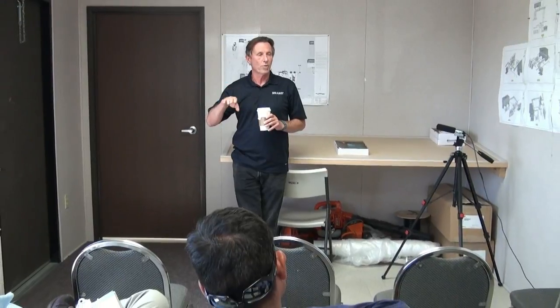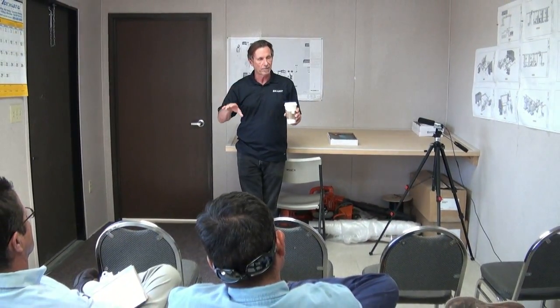That's a good question. As the compressor is spinning, there's a certain amount of kinetic energy in that shaft that's spinning. As soon as the compressor senses a power loss, this is part of the logic, part of the safety in that compressor, it instantly goes into a generator mode. So it produces enough power to keep the capacitor bank charged long enough for the compressor to safely slow the shaft and delevitate the shaft, and it'll set down.